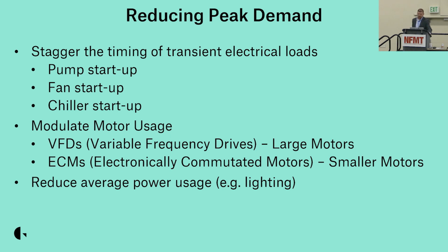So some of the things you can do to bring down that peak demand: stagger the timing of the loads. That's what we did in the morning. That's for everything. Pump startups, stagger those. Stagger the fan startups, chiller startups. Basically, you're just trying to give the building time to get up to speed instead of hitting it all at once.